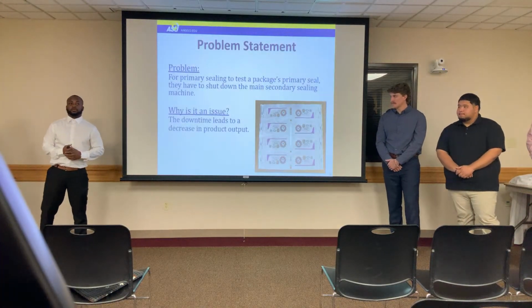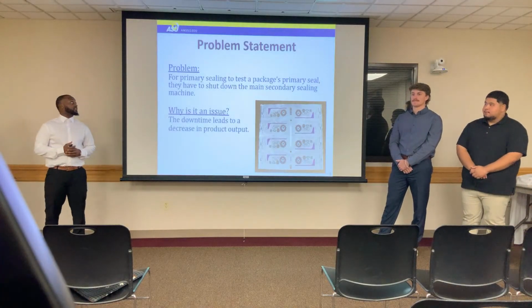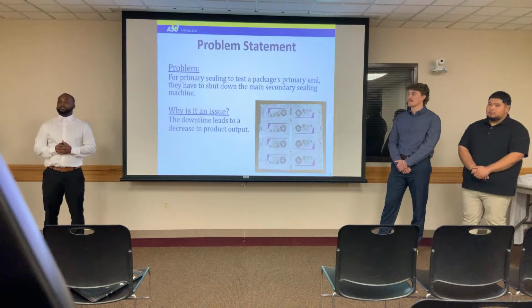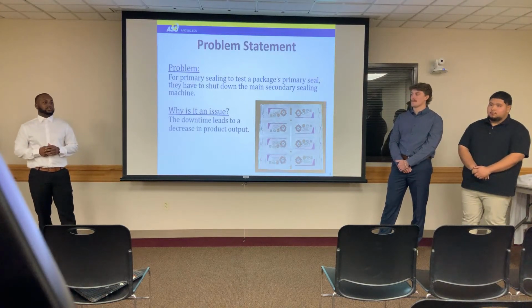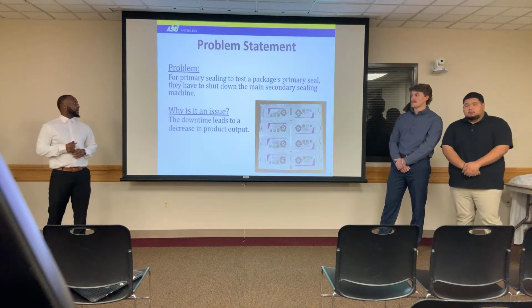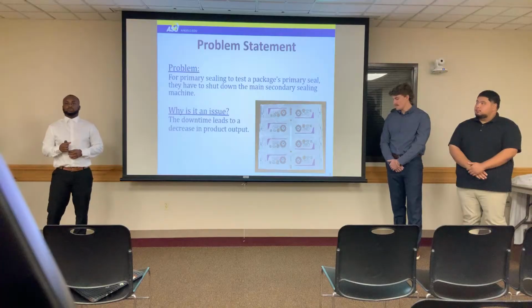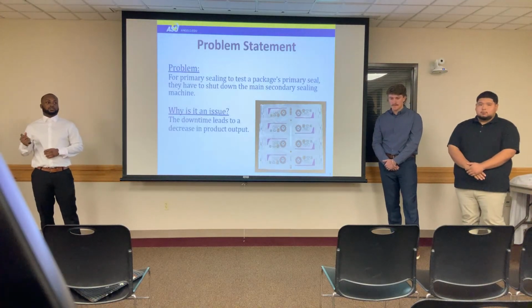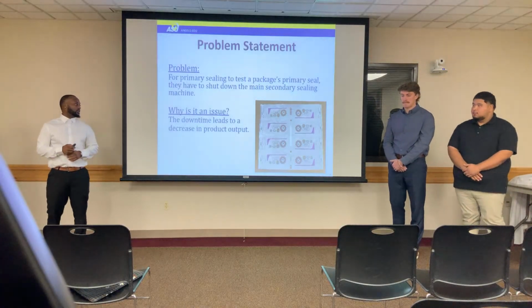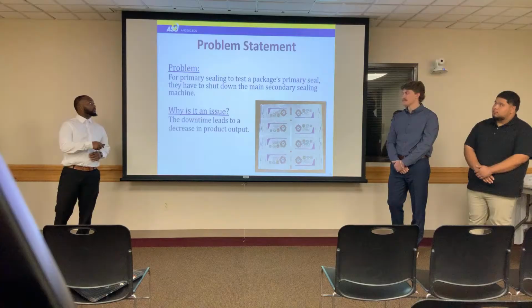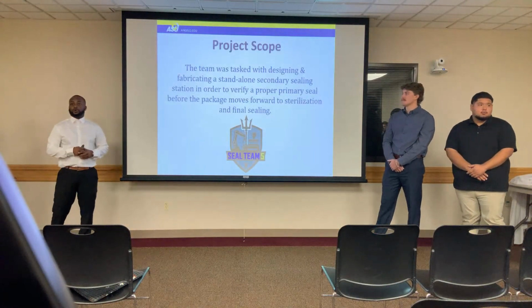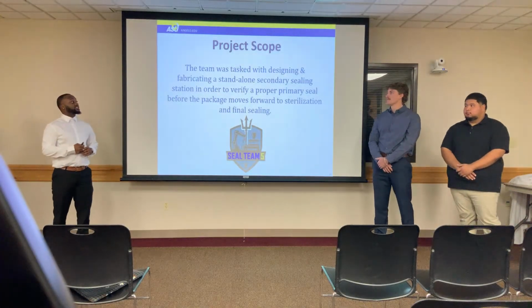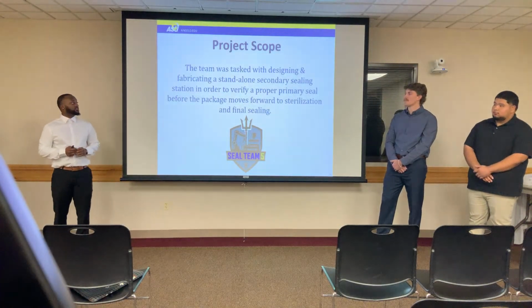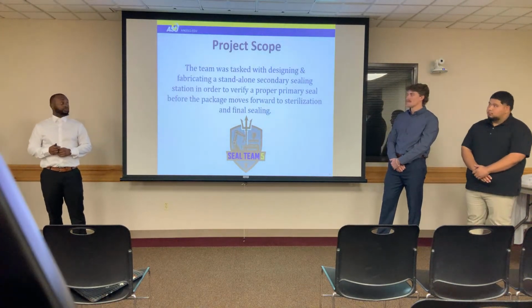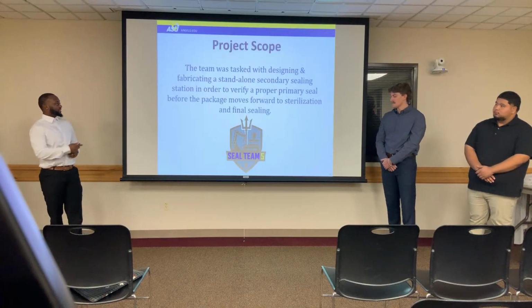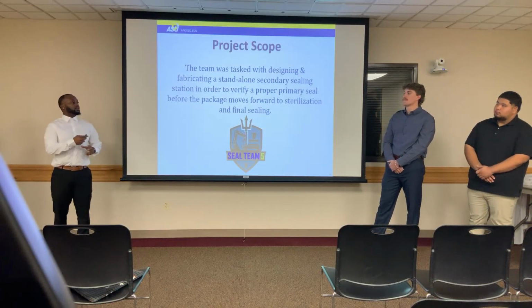All right, next we have our problem statement. The main problem that MedTech has is to test the primary seal. They have to completely shut down the secondary seal machine to make sure the primary seal is correct. And why is that an issue? This facility produces about 1/3 of the sutures in the whole world, and any downtime leads to a decrease in product output. All right, next we have our project scope. Our team was tasked with designing and fabricating a standalone secondary seal machine to be used to test primary seals for the primary sealing department before the packages move forward to sterilization and final seal.